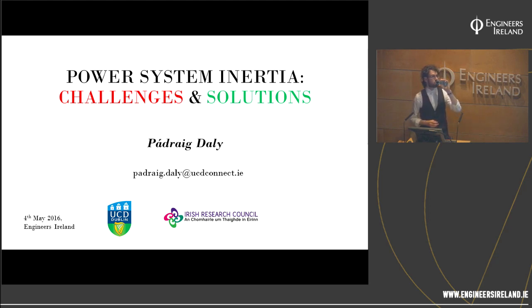Second thing is, EirGrid in their December publication last year seemed to be singularly unimpressed by synthetic inertia. And certainly, reading the paper, they went through a whole pile of options, and my impression of it, whether it was my misreading or their intention, was they weren't terribly interested. And we do have a significant opportunity to provide synchronous condensers in this country, in that we have a whole pile of surplus synchronous generating capacity that actually isn't operated at all. The barrier to doing that is the capacity payment that these generators receive at the moment and wouldn't receive if they were doing something useful as a synchronous condenser.